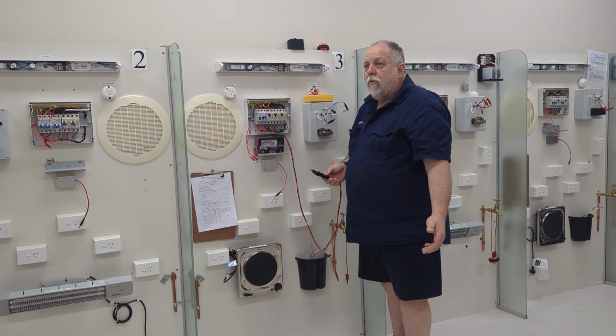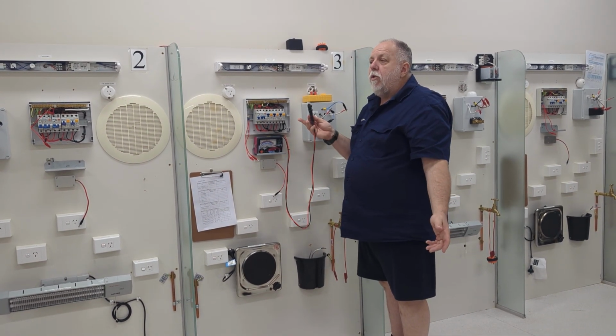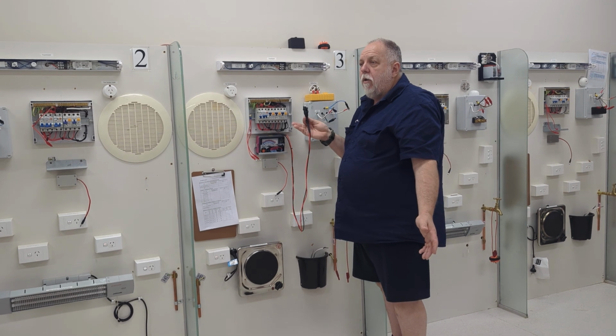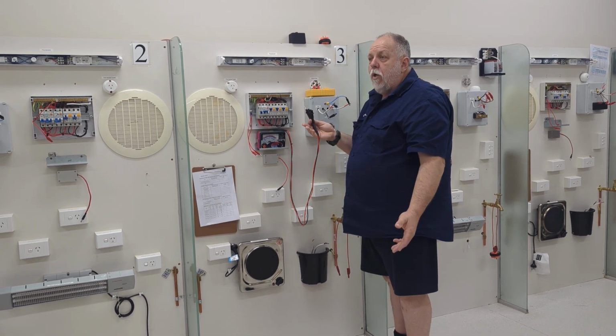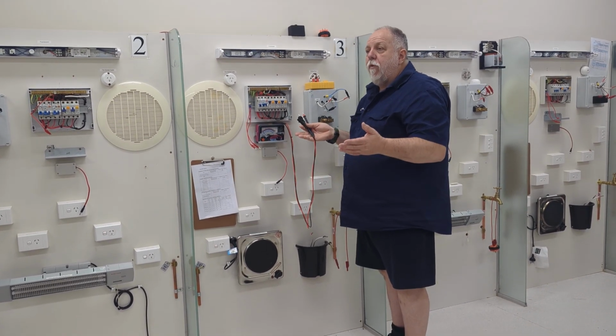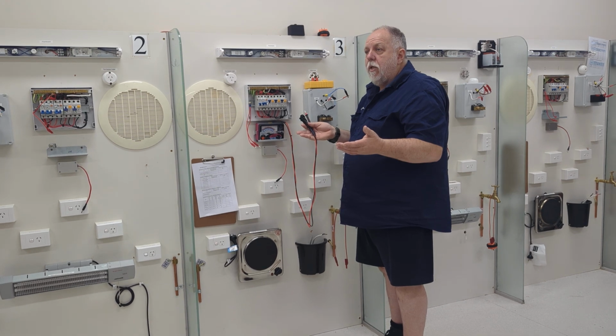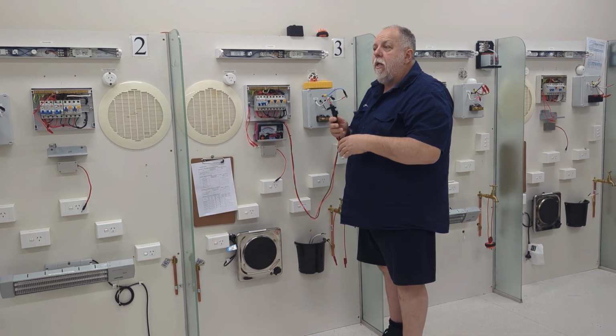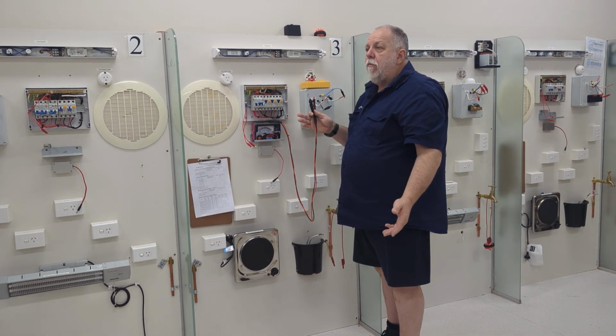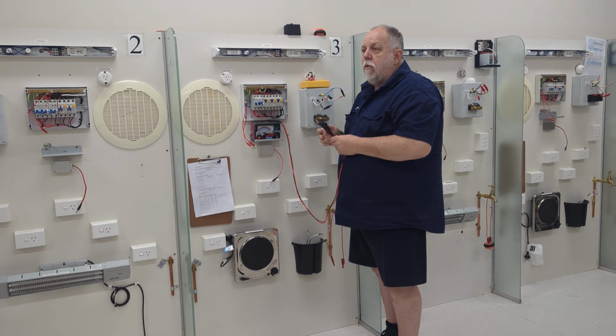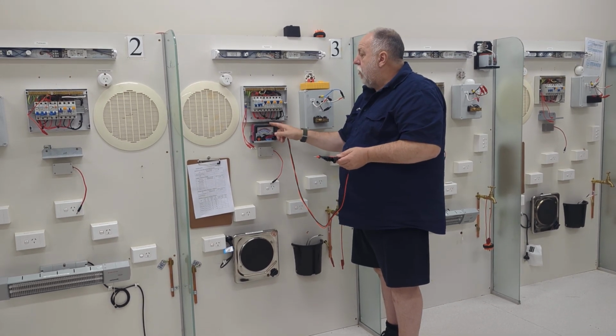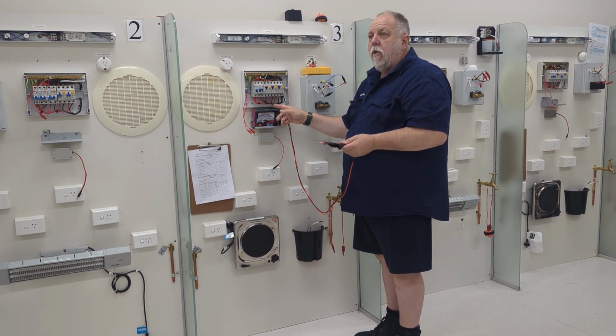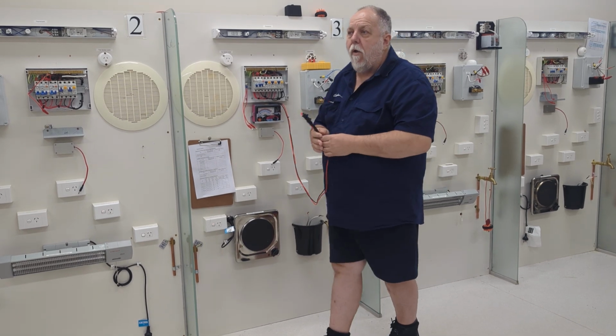It's too high. Sorry? Because everything we're doing is to earth, so it's 500 volts, right? Double the pressure. 240 volts to earth. If we're doing 1,000, it's phase to phase. Does that make sense? So when you're testing anything to earth, we just do 500 volts. If you're testing phase to phase, we do 1,000. It's double the pressure. This is all DC, all right? It's not AC. Why do we use DC?